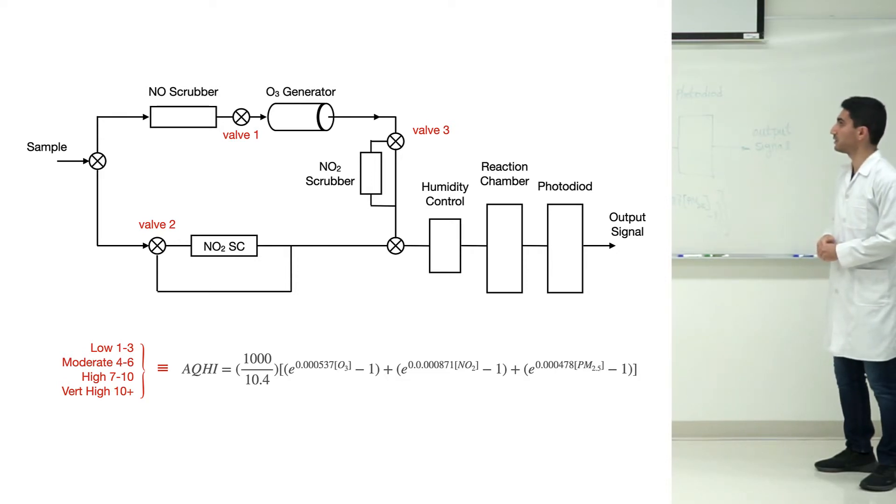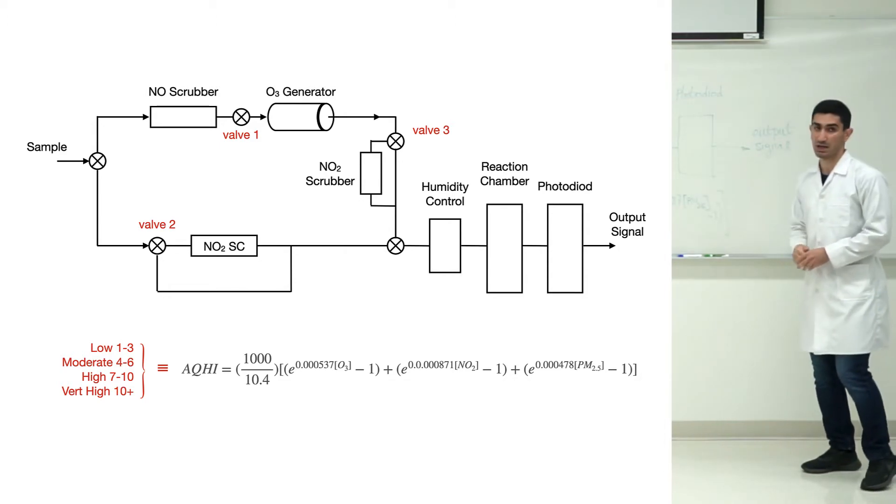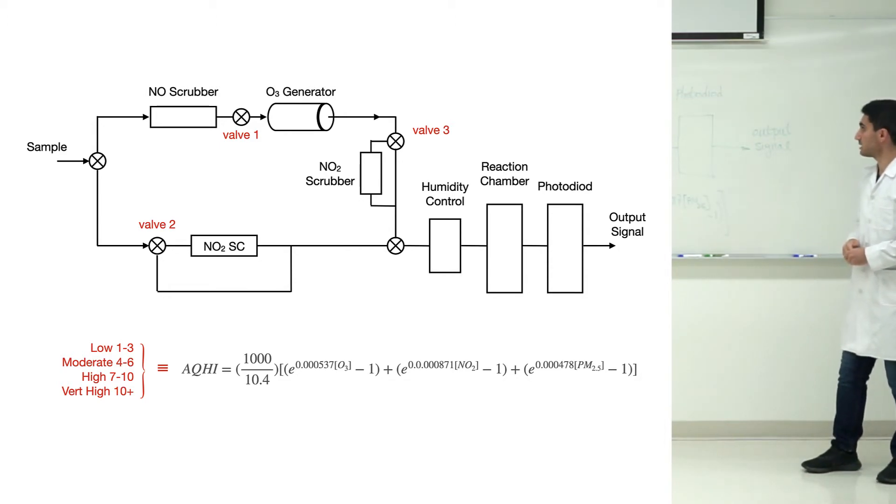Why do we have a reaction chamber? To turn all the nitrogen monoxide into nitrogen dioxide and measure total NO2 concentration, we need a reaction between ozone and nitrogen monoxide. The reaction chamber does this for us.